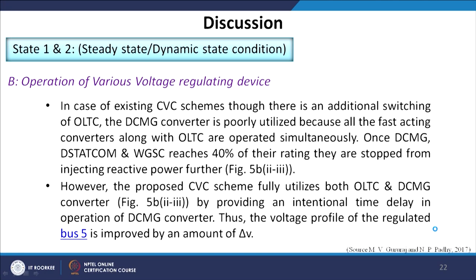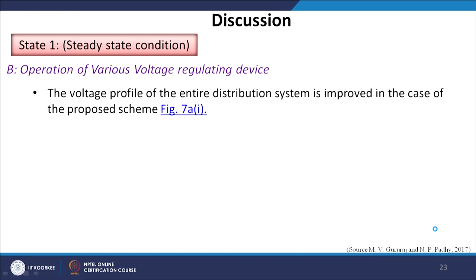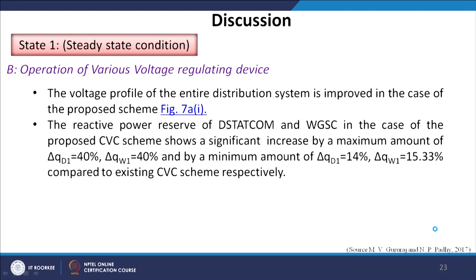The major problem is that they all act simultaneously — the moment they reach 40 percent capability they are no longer allowed to act. However, the proposed CVC scheme fully utilizes both OLTC and DC microgrid converter by providing an intentional time delay in operating the DC microgrid converters. Thus the voltage profile of regulated bus 5 is improved by an amount ΔV. The reactive power reserve of the DSTATCOM and wind generator shows a significant increase by a maximum of ΔQD = 40 percent and ΔQW = 40 percent, and by a minimum of 14 percent and 15.33 percent respectively, compared to the existing CVC schemes.